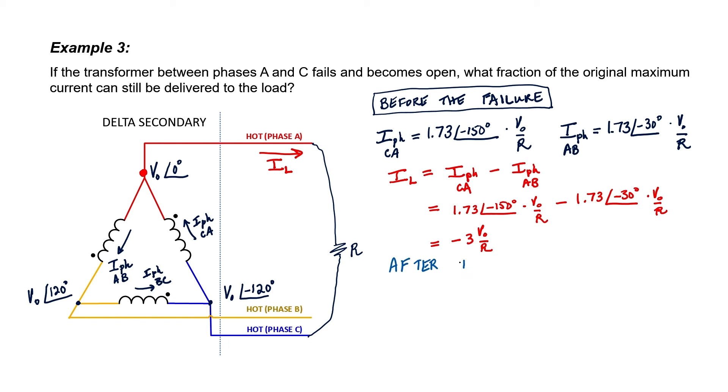Let's now consider what happens after the failure. If one transformer out of the bank of three fails, one of the advantages of the delta configuration is that the voltages are still there. You can get by with just two out of three transformers.